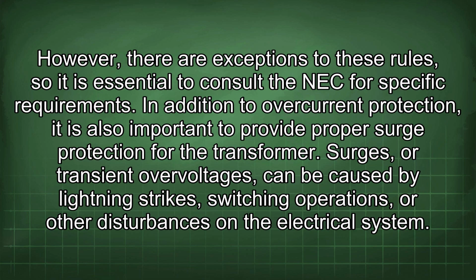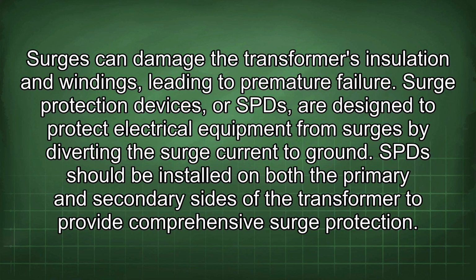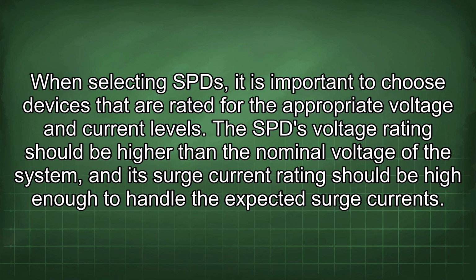Surges or transient overvoltages can be caused by lightning strikes, switching operations, or other disturbances on the electrical system. Surges can damage the transformer's insulation and windings, leading to premature failure. Surge protection devices, or SPDs, are designed to protect electrical equipment from surges by diverting the surge current to ground. SPDs should be installed on both the primary and secondary sides of the transformer to provide comprehensive surge protection. When selecting SPDs, it is important to choose devices that are rated for the appropriate voltage and current levels. The SPD voltage rating should be higher than the nominal voltage of the system, and its surge current rating should be high enough to handle the expected surge currents.